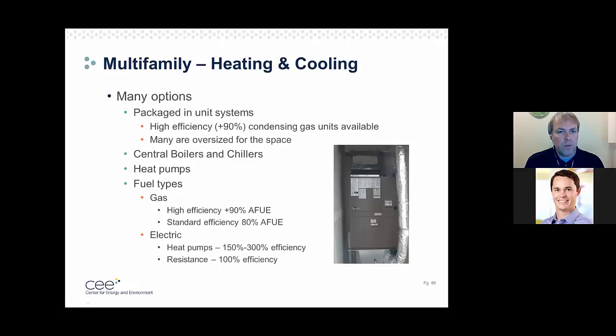And a step now into multifamily heating and cooling. There are many options out there in the market. We're seeing a lot of packaged in-unit systems. There are higher efficiency models now with condensing gas units available. The problem we're seeing with a lot of these is that they're just oversized for the space. Buildings have become more efficient, they're tighter. And you're trying to move all the CFM that's needed through the heat exchanger and the coil, the cooling coil. It's heat and cool, and it's just really hard to do with a system this size.